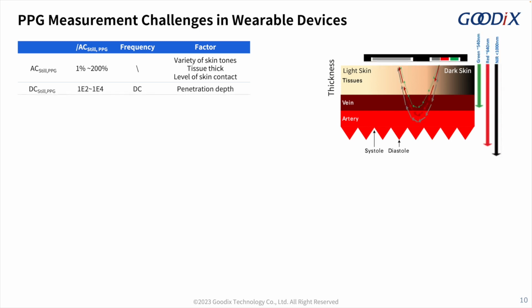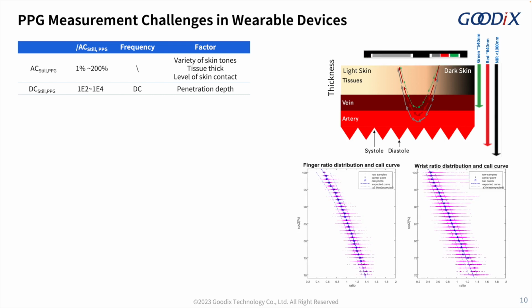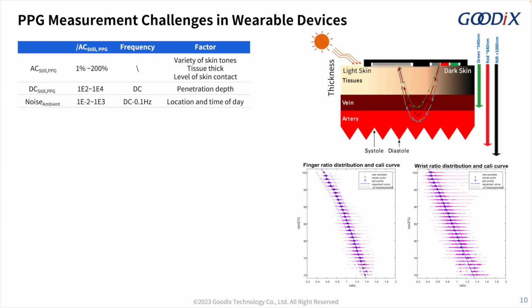The DC amount of different light sources varies greatly due to the difference in the depth of light penetration through the skin at different wavelengths. That can cause a large difference in the optical path in wrist reflected measurement, which in turn leads to a large fitting dispersion, making it easy to obtain false oxygen measurement results. The ambient light changes greatly. In different environments, in daily use scenarios, the ambient light will fluctuate greatly as the user moves to different locations.